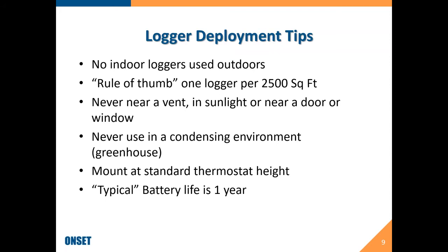Where do you mount your loggers? You usually mount them at a standard thermostat height, right at eye level, thereabouts. I've answered some of the questions that were written in earlier, one of which was how long does a typical logger run for? The typical battery life is 1 year. Here at Onset, we try to ensure that every logger at least has a 1 year battery life if possible, with a logging rate of once a minute. So we try to maintain that in all of our loggers if we can.